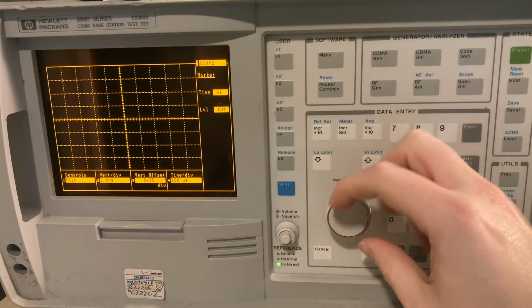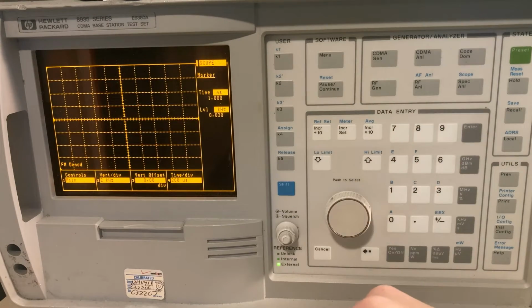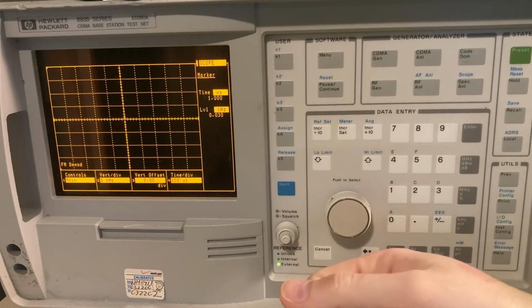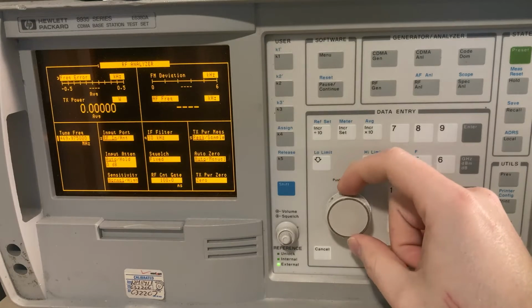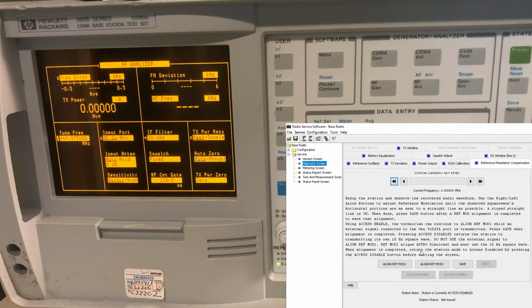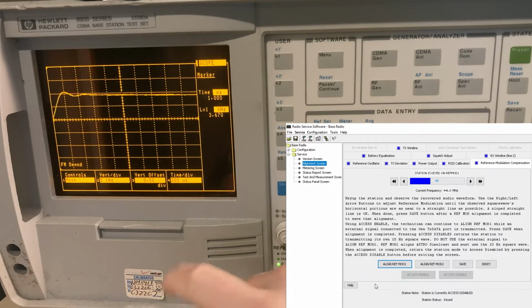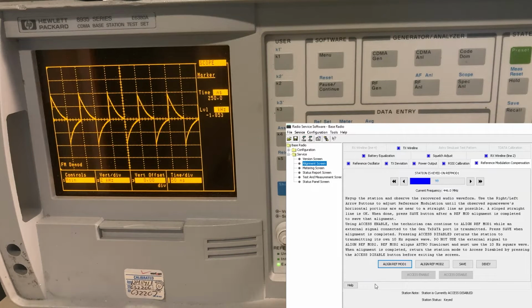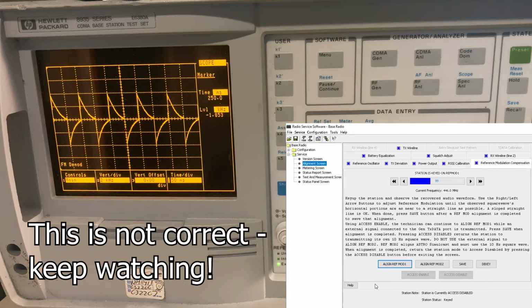So we'll go into scope mode here. And you'll notice it says FM demod on there, which means it's pulling in its input from the FM demodulated audio. And I'll go back into the RF analyzer screen because I will have to change the tune frequency. And we'll go ahead and click Align Ref Mod 1, which will key up on the test frequency of 446 megahertz. We'll type in 446 megahertz, and we will go back to scope mode. And we'll have to adjust the triggering a little bit, adjust the time per division. There we go, 50 milliseconds. And we've got a, not a very square wave there. So basically the goal here is to try and get that to look as close to a square wave as we possibly can. So I will play with the values here, and you'll see how it affects the shape of the waveform.